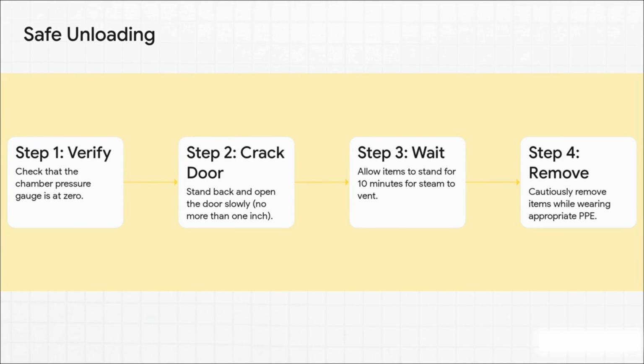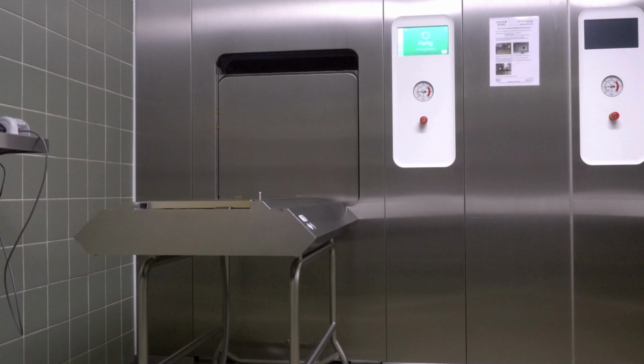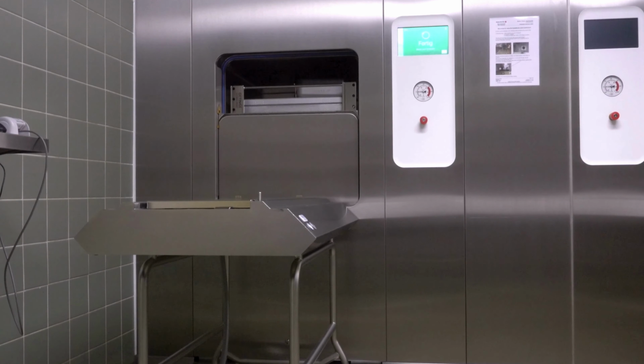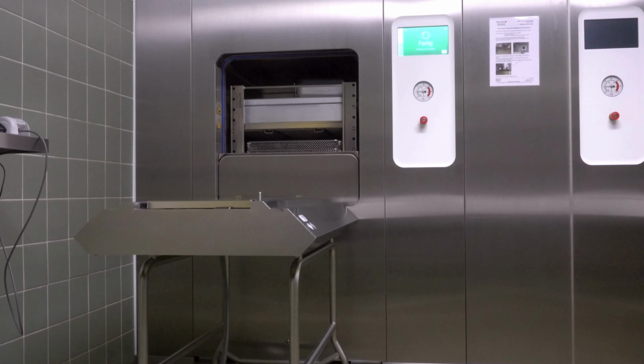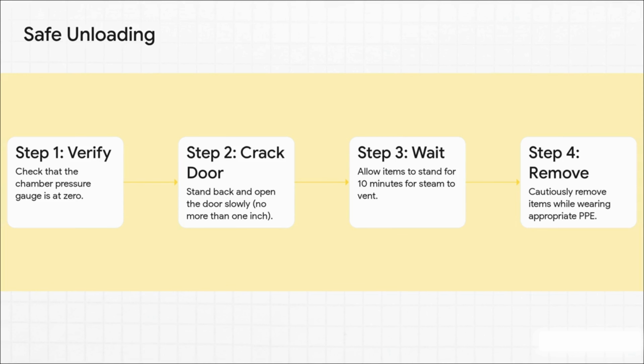And the danger is not over just because the cycle has finished. Unloading has to be done by the book every single time. Step 1: make sure that pressure gauge reads zero, no exceptions. Step 2: stand back and crack the door open just an inch or so, to let that superheated steam start to vent. Step 3: now you wait, a full 10 minutes — rushing this step is a huge mistake. Only then, with all your PPE back on, can you safely start to remove the items.